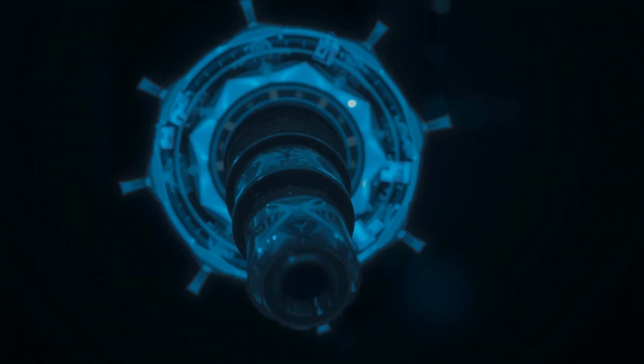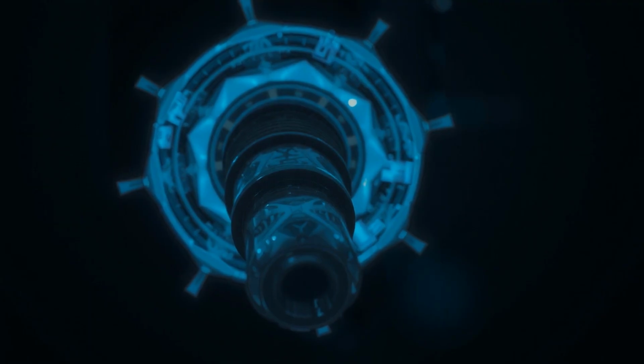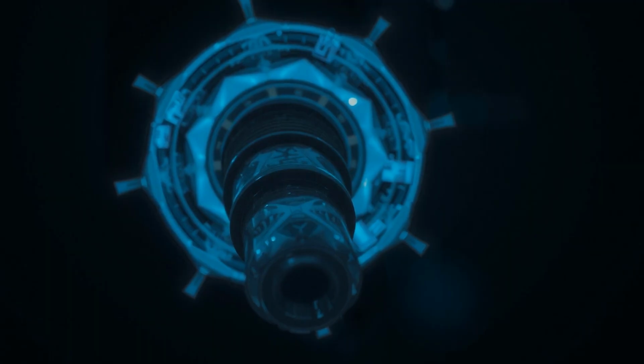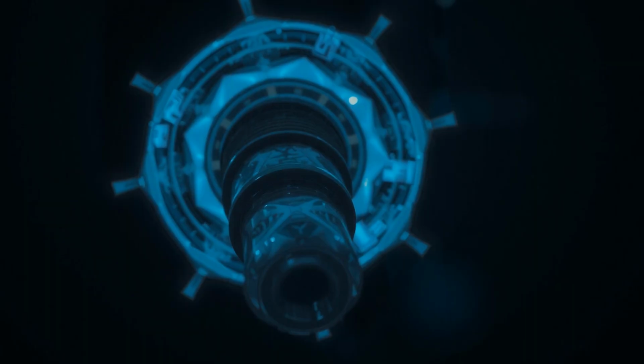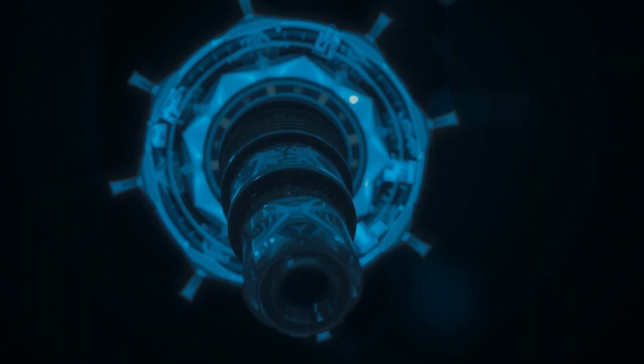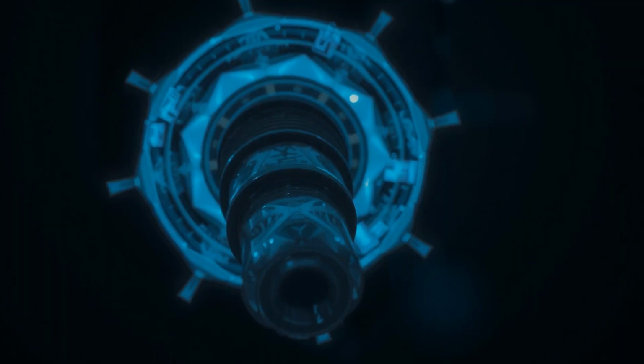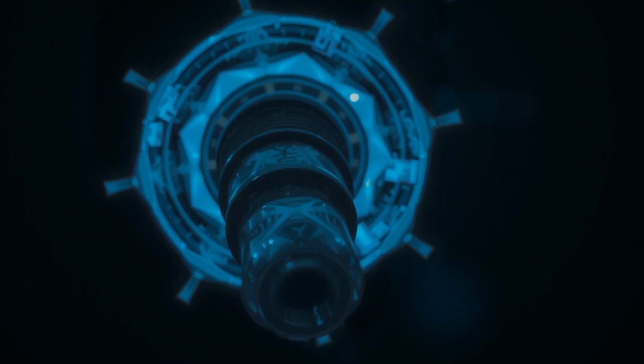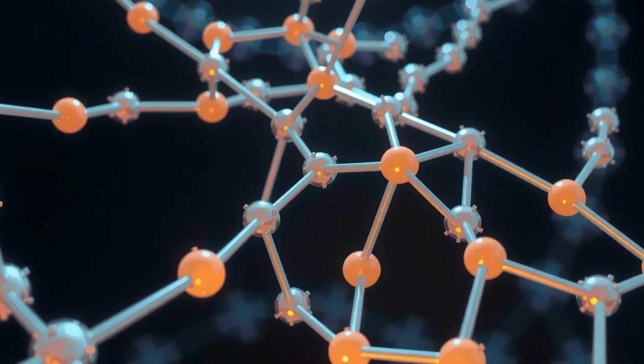To move huge amounts of power efficiently over a long distance, you have to use very high voltage. But high voltage inside a cable buried under salt water is a destructive force. The electric field wants to tear through anything around the conductor, and if the insulation fails, the cable shorts out, and repairing a fault under 60 meters of ocean can cost tens of millions of dollars and months of lost generation. So the insulation has to be nearly perfect, mile after mile after mile.